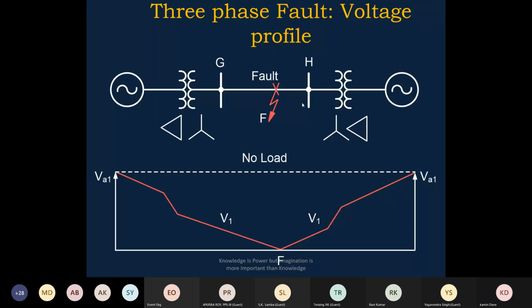So look at it here. There is typically a two-bus system, two generator, two source system, two sources, two buses, G and H, and there is a line between the G and H bus. So when there is a fault F, at the fault location the voltage is almost zero. Look at it here. Voltage is almost zero. The positive sequence voltage is almost zero. When you go far away from this fault location, the positive sequence component is getting increased. V1 voltage at both ends.